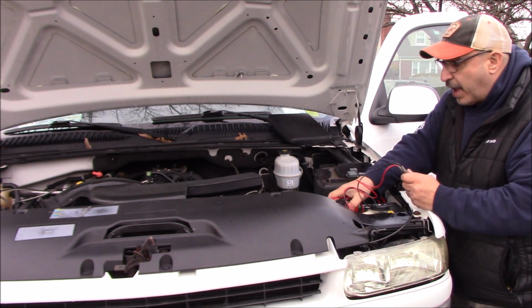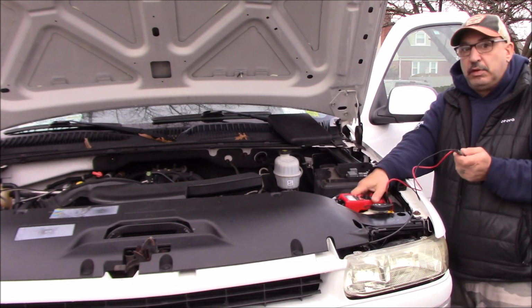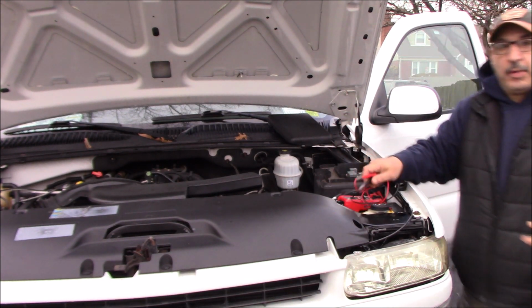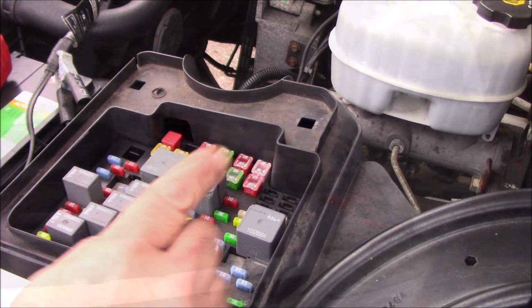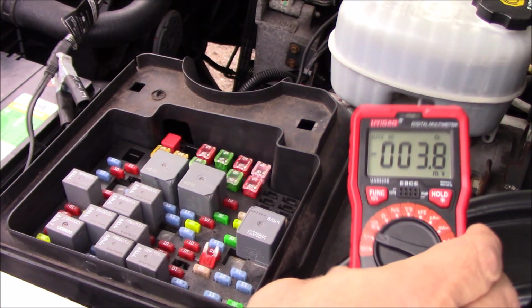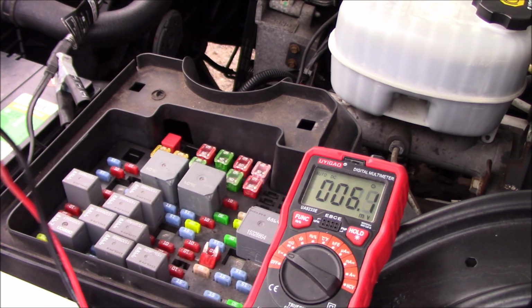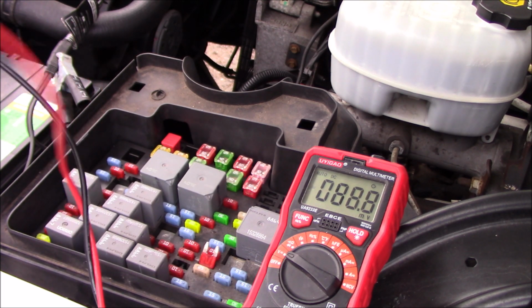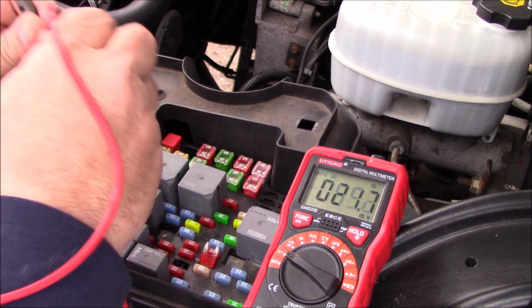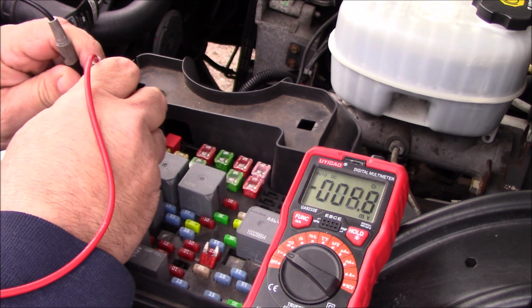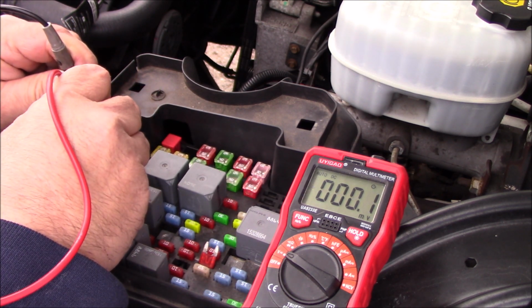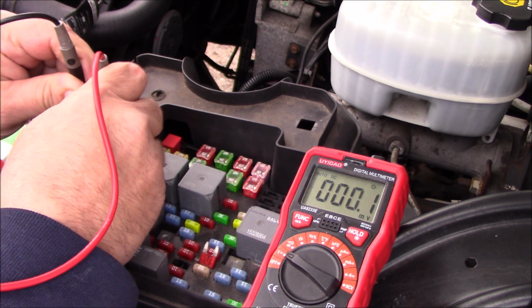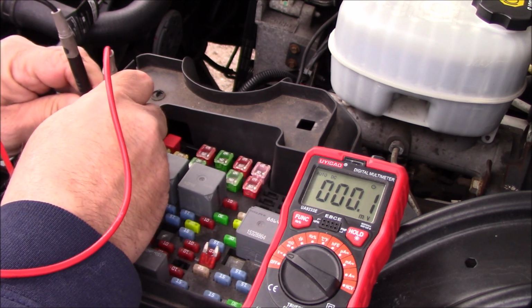So what you're going to do is put your meter on a millivolt scale — let me bring the camera in here. With your meter on DC millivolts, you touch the tops of your fuses going across the fuse, and you'll see a number go up, and then it will go down to either 0.1 or 0.